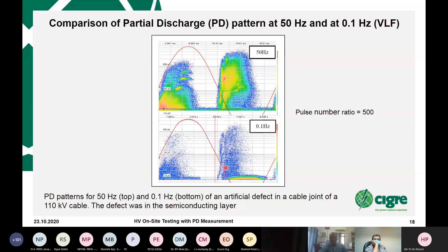This is also a typical pattern figure shown in this technical brochure. For high voltage components, is it new or in service? For new equipment at the factory, you can make these measurements in frequency or time domain. That means looking at a typical pulse and the apparent charge.